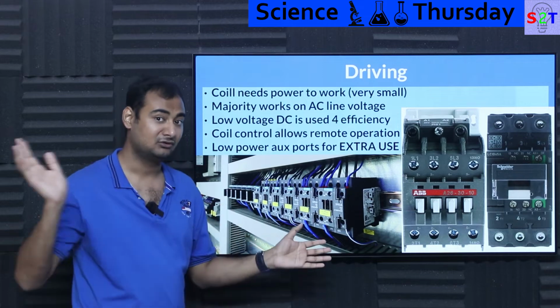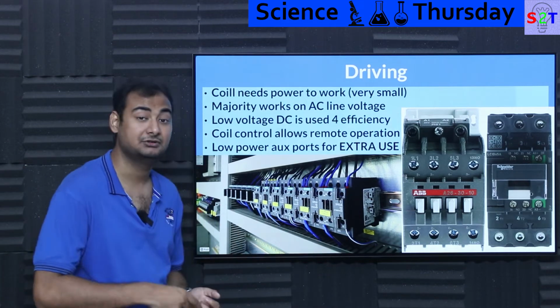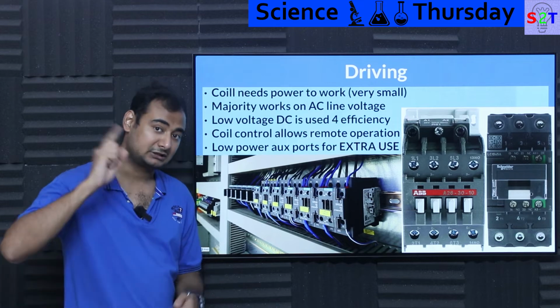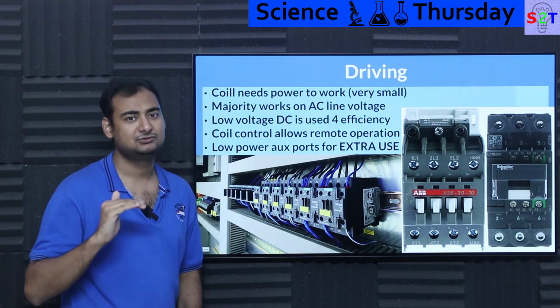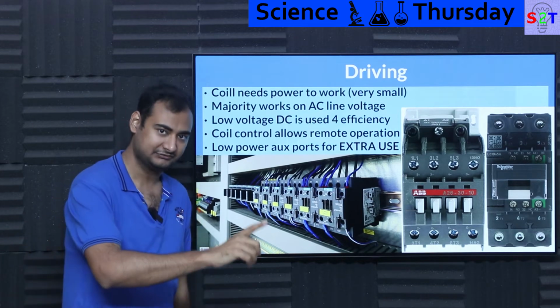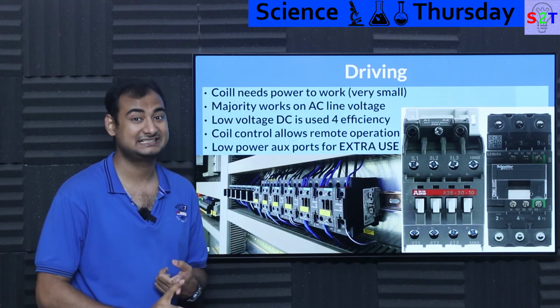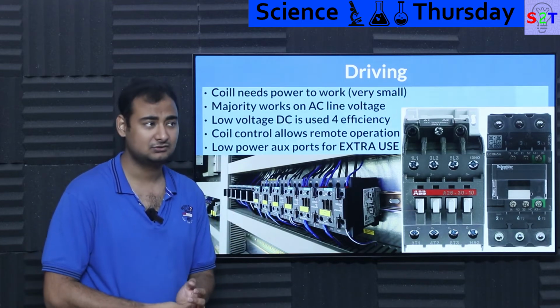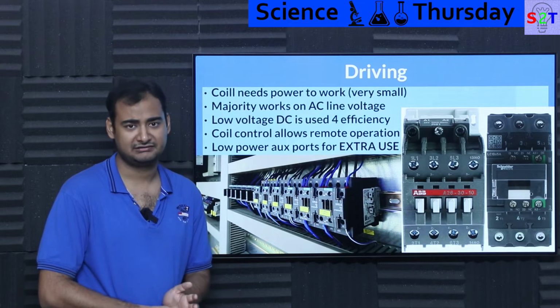If you are dealing with long wiring runs, you generally have to go to 48 volts. If you are dealing with power over Ethernet, it can also go up to 48 volt. Generally people do not want to exceed 48 volts because past 50 volts it can cross your skin. If you are ever touching 48 volt, chances are you will survive with no issue.